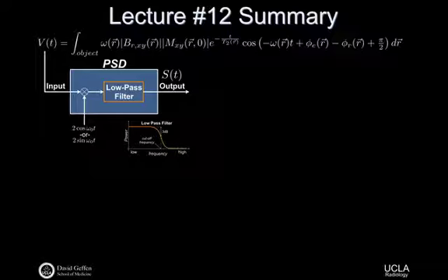And so the idea is that this rather big expression now is the voltage that is the input to this phase-sensitive detector. The phase-sensitive detector is just going to take that input signal, multiply it by a cosine omega naught or sine omega naught term. And that's going to give us two signal terms, a pretty low frequency term and a really high frequency term. And the consequence of that is we can use a low pass filter to get rid of the really high frequency stuff and just keep the lower frequency stuff. And the lower frequency stuff will be the spatial frequency information that we care about. It'll contain a term that looks like omega as a function of spatial position, some spatial encoding information. And the super high frequency information is not useful to us, we filter it out.